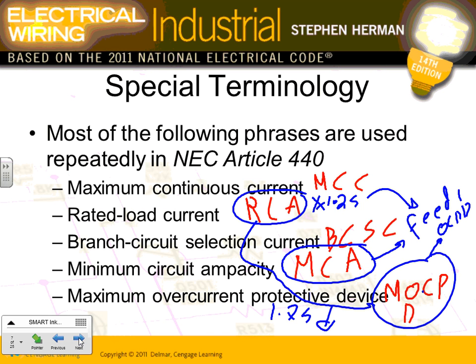Then they have maximum continuous current. The manufacturer runs the equipment, they measure the largest current that the equipment can handle before it blows, basically, and they give a value of that. That's called maximum. Typically not for us, we don't use it a lot. For them, rated load current is, remember, a percentage of the maximum continuous current.